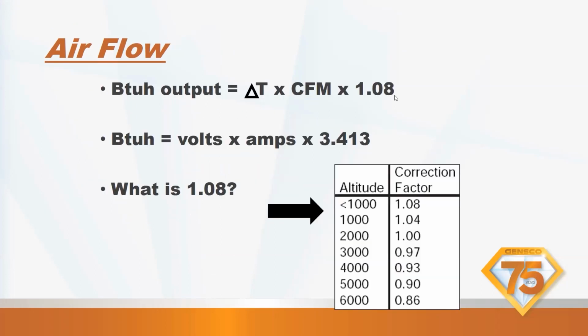And then put in your correction factor and see how many CFMs are different. I've been to places in Montana where we do that calculation at 4,000 feet elevation, and we're 600, 700, 800, 1,000 CFMs off of what it's set up for at the factory. Okay, so just because it says 1,600 CFMs when you set it up, it doesn't mean it's actually putting out 1,600 CFMs. So you need to do some kind of a test to verify your airflow.